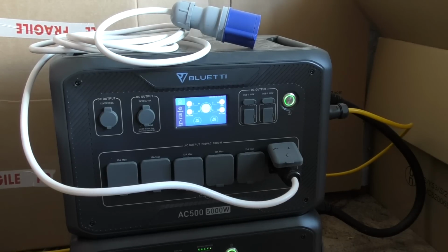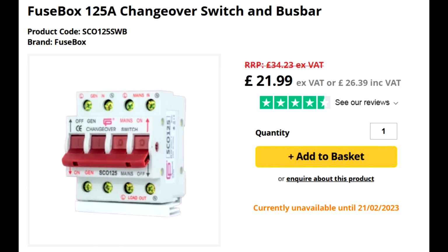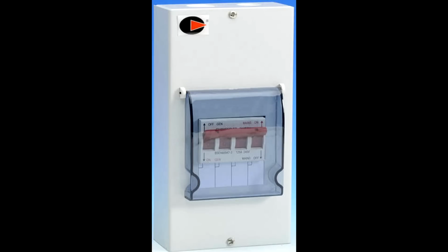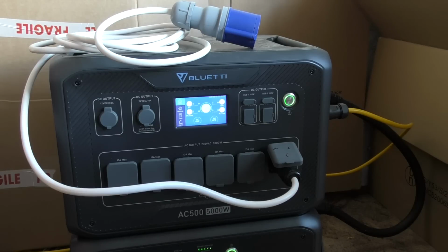So I had a look around at what's available in terms of just physical switches. Now the only thing I could find from UK supply was this. This is a two-way, two-pole isolator switch rated at 125 amps. This is available both as a single unit and also a complete unit in a box. When I was looking, I couldn't actually find the separate unit in stock anywhere, but I'd also had a look around to see what I can find elsewhere, and there's a couple of devices on AliExpress. One was a simple changeover, which is what I eventually used, which I'll show you in a minute. The other one was this.